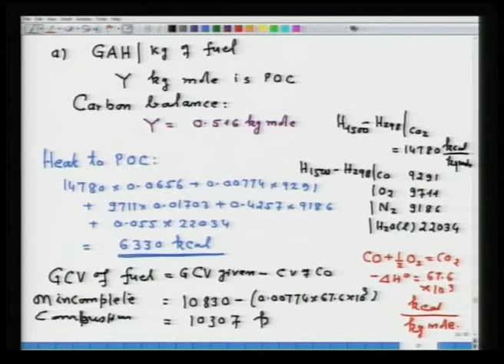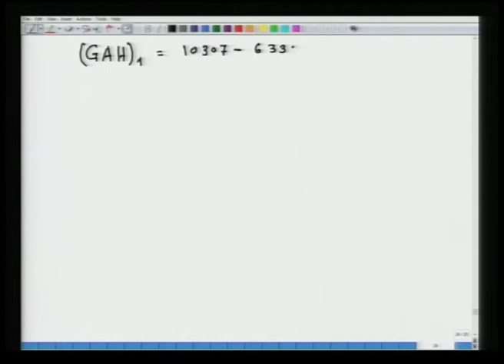So, what we will do now: GCV given is 10,830, minus the calorific value of CO, which will be 0.00774 into 67.6 into 10 to the power 3. That brings us to the gross calorific value available for A, that is 10,307 kilocalorie. Next we have to calculate the gross available heat, which is what is being asked. So, gross available heat 1 will be equal to 10,307 minus 6330, that is equal to 3977 kilocalorie.